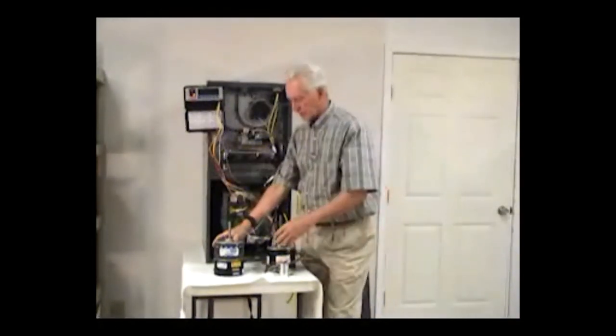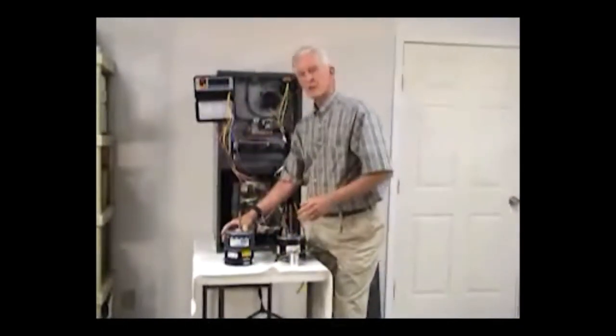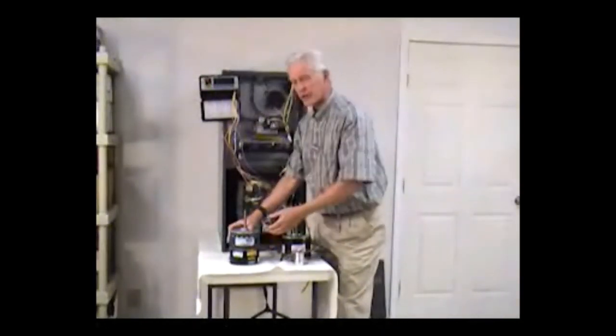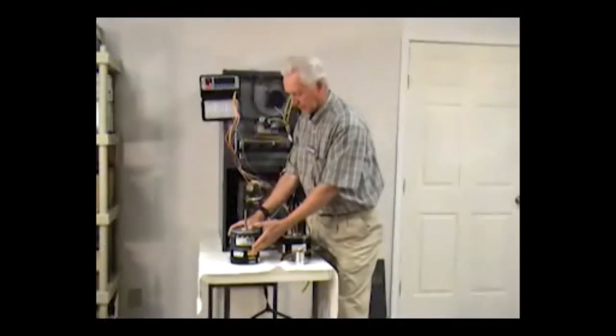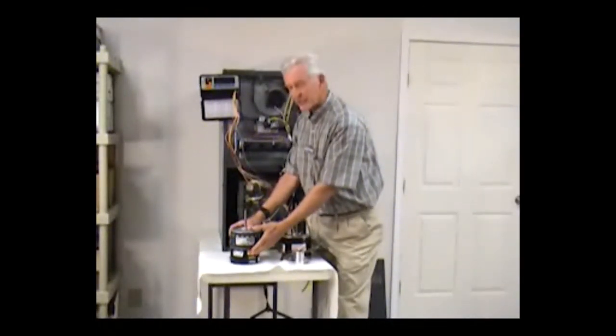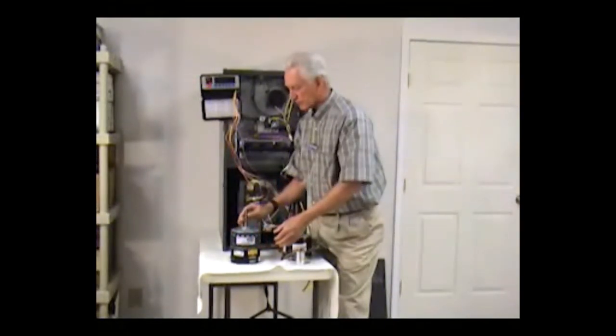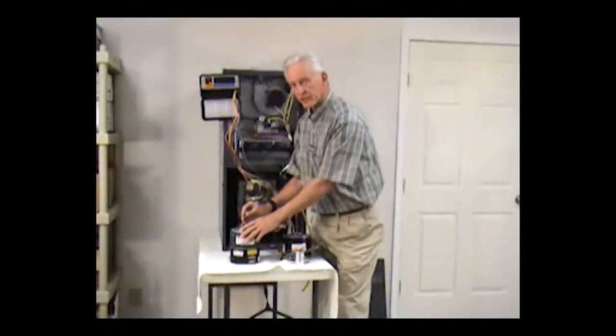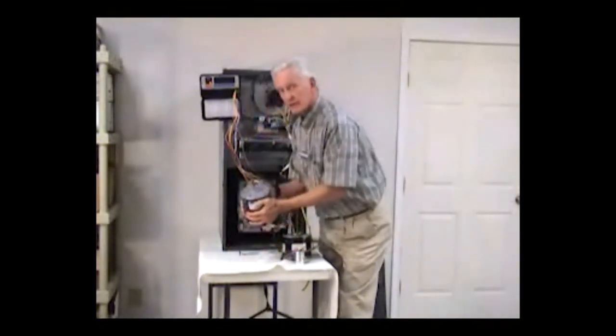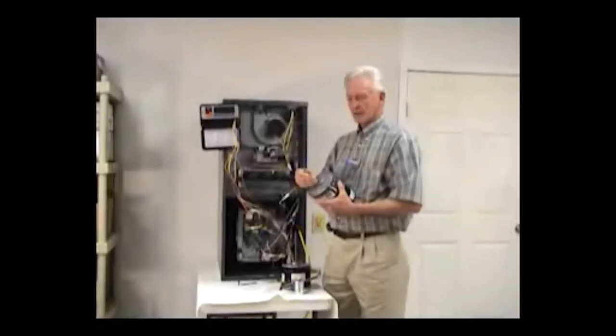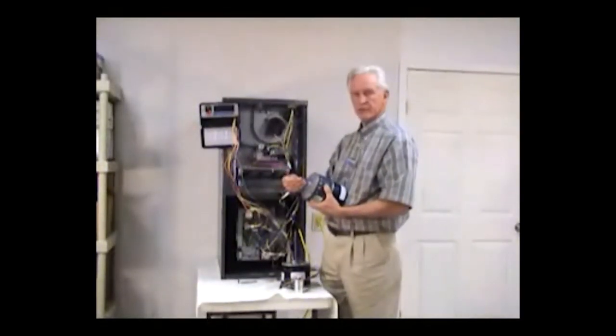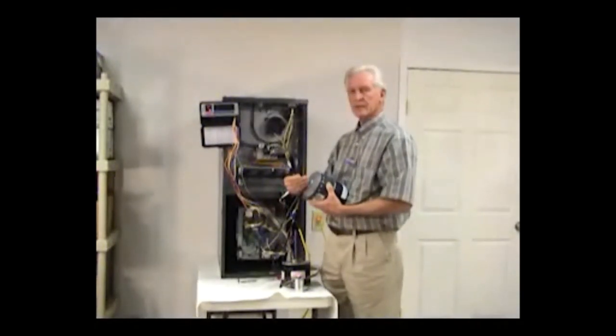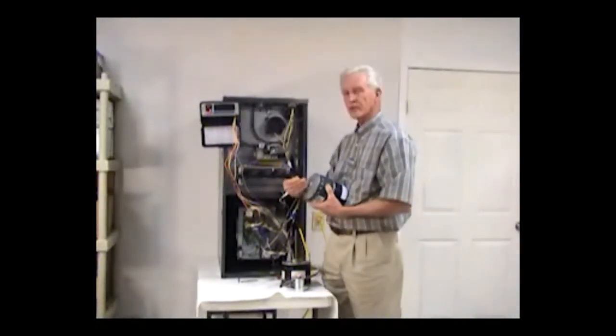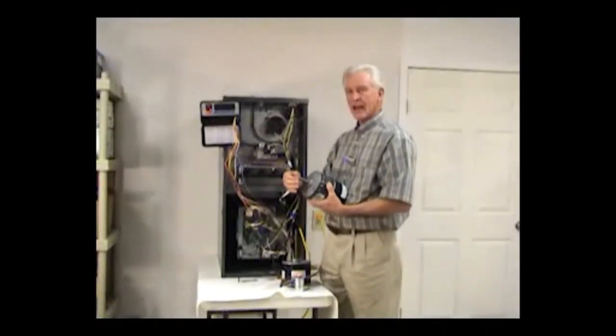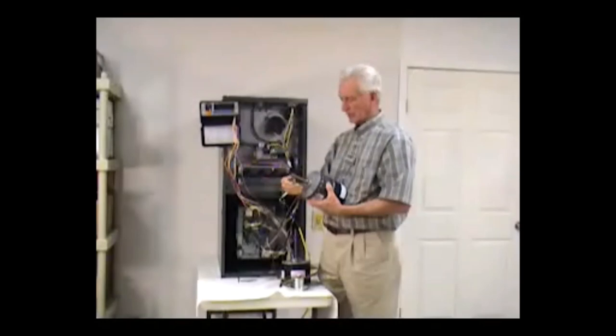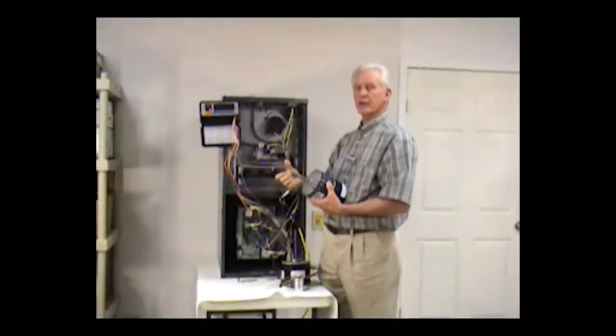Another thing that we need to know that is characteristic of this motor during a failure, which we will mention when we start talking about modules again later on in the service aspect of this, is that in some cases when modules fail, technicians will actually take the motor itself with the module attached, and they will turn the shaft, and they will find that it doesn't turn as easy as this one turns right now, but that you have to take a tremendous amount of tension or force to actually make the shaft turn. And it is a natural thing for technicians to, and I do it all the time, turn the shaft of the motor to see if it turns freely.